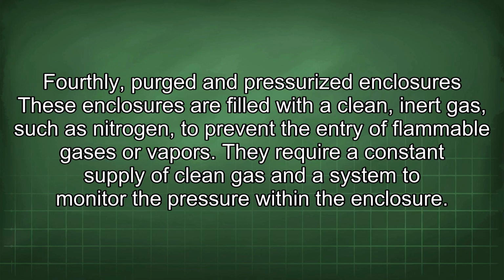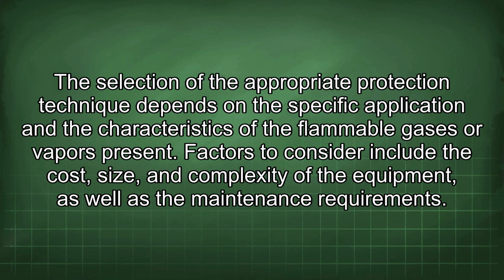Fourthly, purged and pressurized enclosures. These enclosures are filled with a clean, inert gas such as nitrogen to prevent the entry of flammable gases or vapors. They require a constant supply of clean gas and a system to monitor the pressure within the enclosure. The selection of the appropriate protection technique depends on the specific application and the characteristics of the flammable gases or vapors present. Factors to consider include the cost, size, and complexity of the equipment, as well as the maintenance requirements.